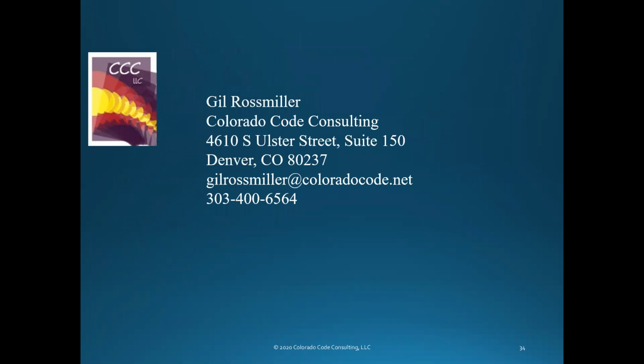What do we got? We got something, Erica, we can talk about? Certainly that we do. We've got a few questions for you here, Gil. Good. First off, how does calculating the new SHR, adding back half the latent capacity, affect your decision for equipment selection? For example, can we just use the original SHR calculation in the selection process?